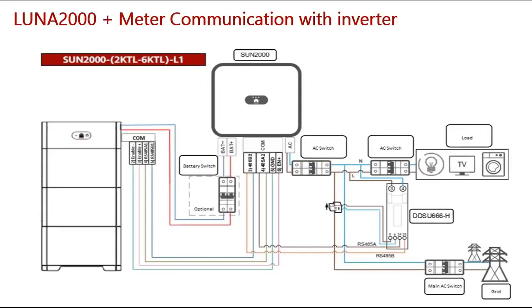So here, pins 2, 3, 4, and 6 will be connected to pins 3, 4, 5, and 6 of the inverter COM port. If you want, you can take a screenshot of this screen, so that you can use it or send it to your installers, because this is the main problem customers are facing: they are confused by the communication connectors of the power control modules with the inverter.